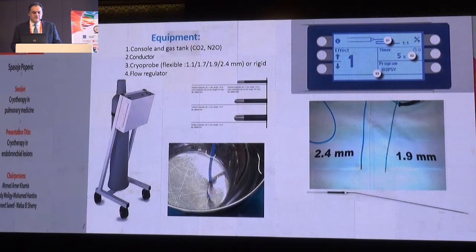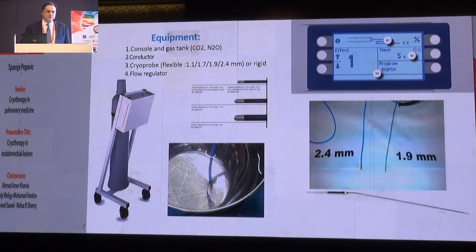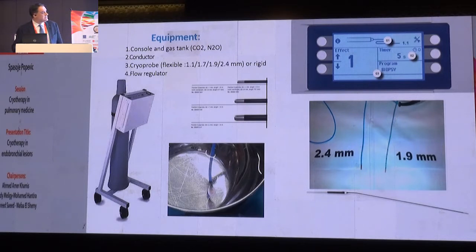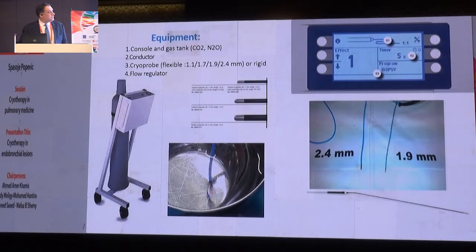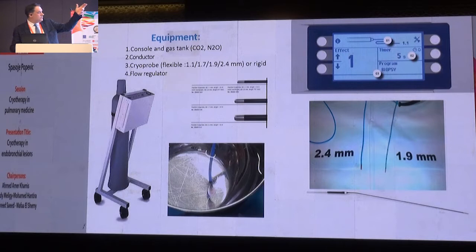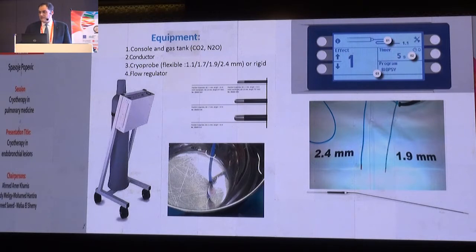The equipment is really very simple. You need a console, a gas tank with either CO2 or nitrous oxide, a conductor, cryo probes of different sizes and diameters. The newest one is 1.1 mm, but they range from 1.1 to 2.4 millimeters. These are flexible cryo probes, and there is also one rigid cryo probe, and a flow regulator.